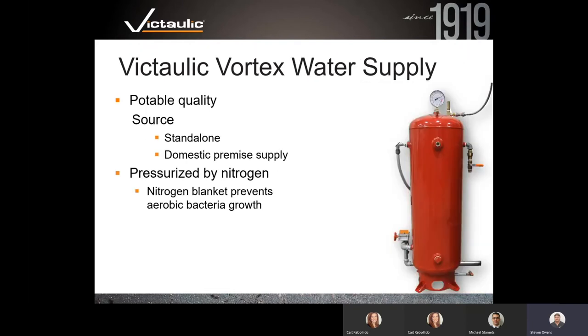The water tank is a 200 PSI ASME-rated vessel with a 150 PSI relief valve and an isolation valve. It is pressurized via a hose off the manifold regulator. Systems have been designed up to 120 PSI water delivery pressure. A check valve holds a blanket of nitrogen on top of the tank after pressurization, which provides immediate pressure and — importantly — keeps the water clean by cutting down corrosion and preventing aerobic bacteria.